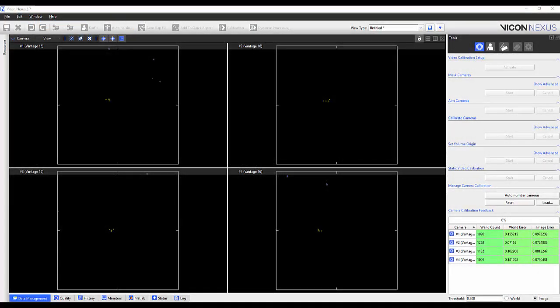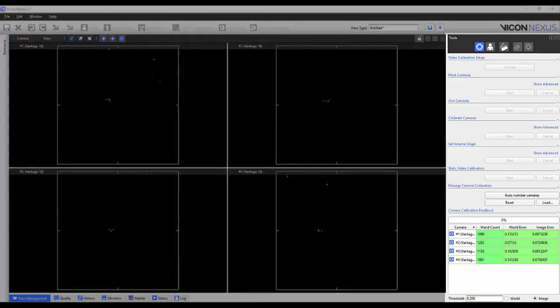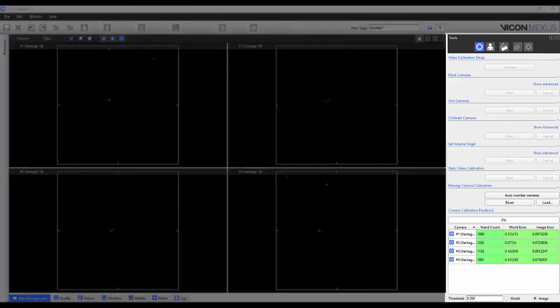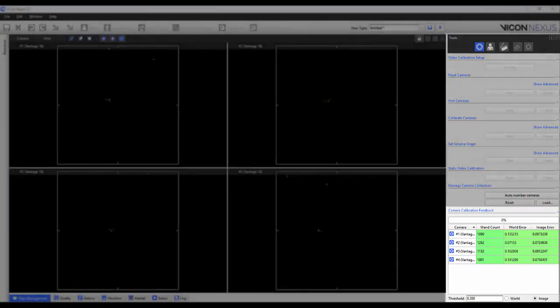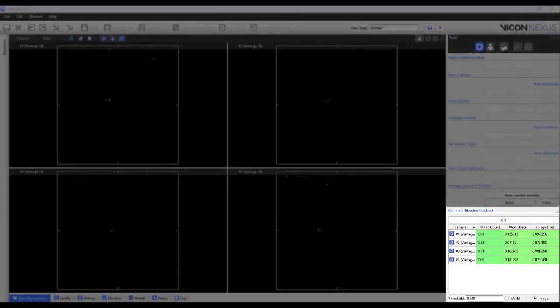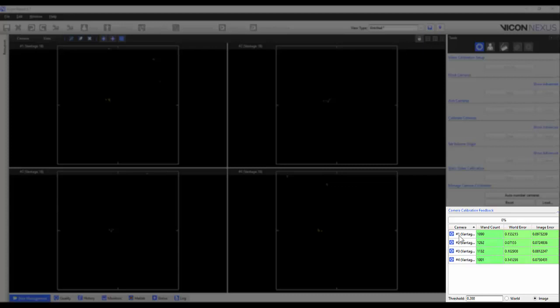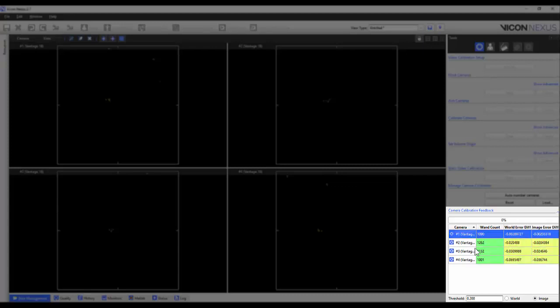All the new calibration feedback features can be found within the tools pane system preparation button. A user can now compare current calibration values with the previous calibration values. To toggle this option on, right click on a camera within the camera calibration feedback table and select show differences.